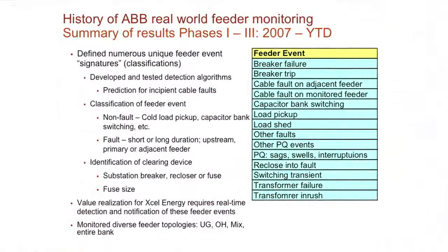So what did we learn in all these three phases? A couple of things: not only were we seeing cable faults, permanent cable faults, and incipient cable faults, but we were seeing a lot of other information with the typical connections available inside a substation on a feeder, at the head of the feeder. We were able to learn a whole list of different types of feeder events. I'm not saying faults — notice I raised it up a level, to a more general term of events.